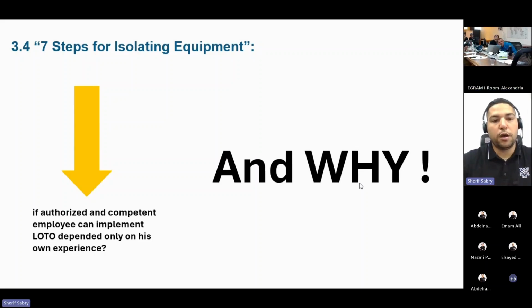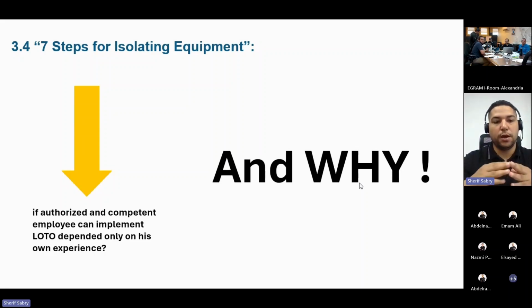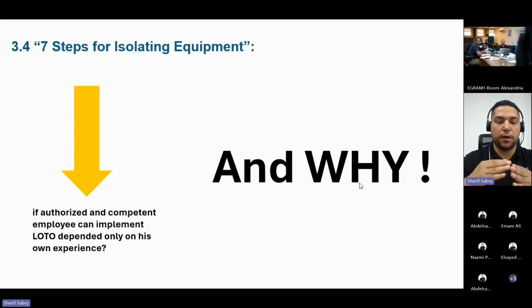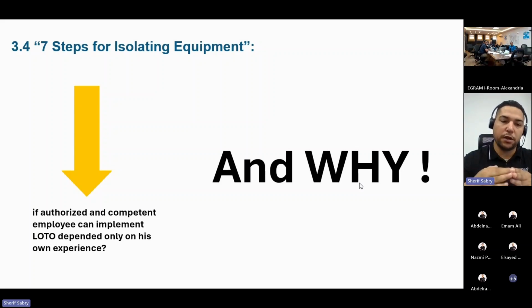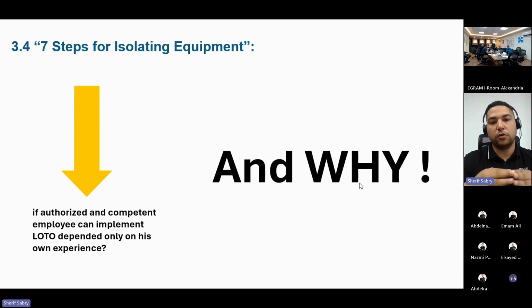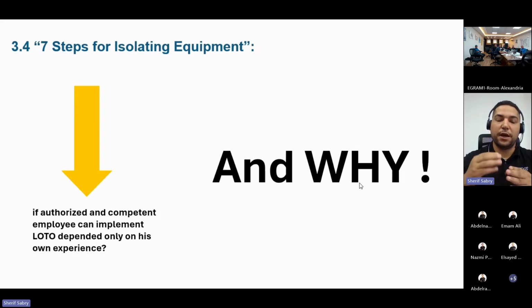Yes, because when you implement LOTO, the authorized and competent employee himself needs to check the LOTO protocol, follow the guidelines, choose the proper equipment, and isolate the energy sources. You need to know everything about the LOTO implementation procedure and guideline, review the guideline and follow the seven steps in isolating the equipment, then depend on your experience in outlining the energy location and source. But the guideline mentions defining the LOTO location and isolation location, then identifying the LOTO location reference to the activity, which is specified for every machine. So your own experience is not the main aspect to depend on while implementing LOTO.